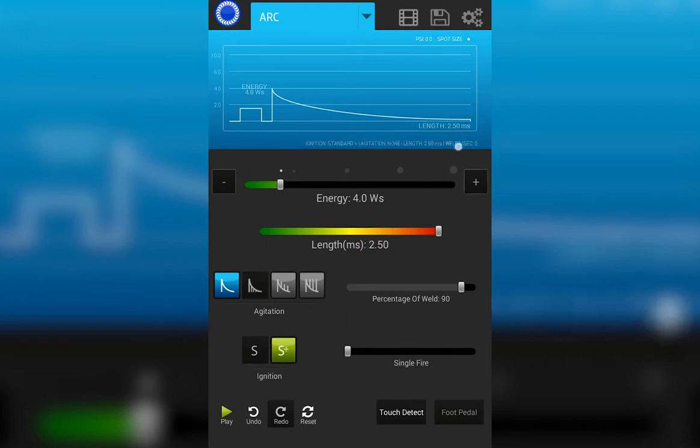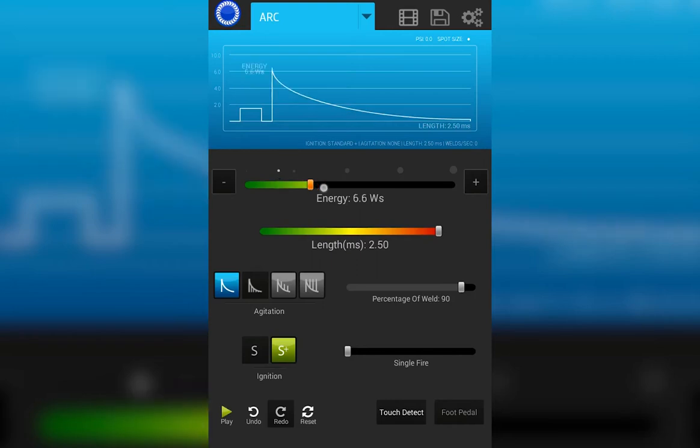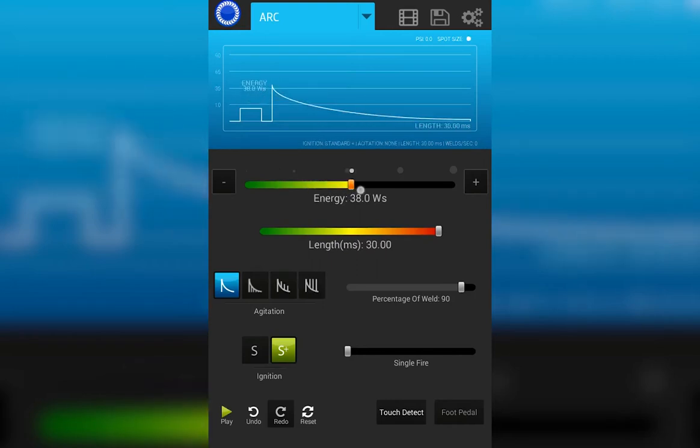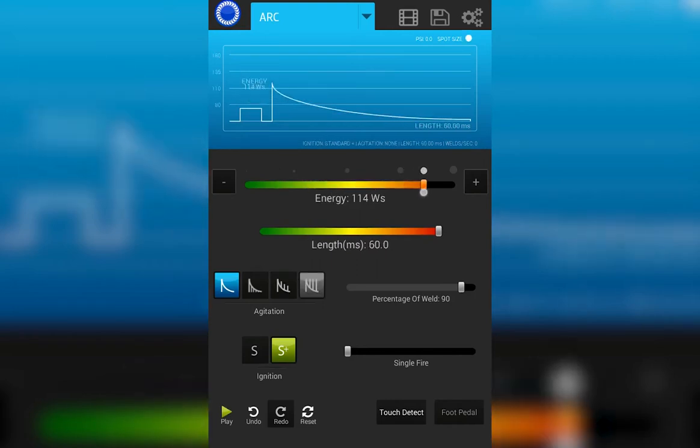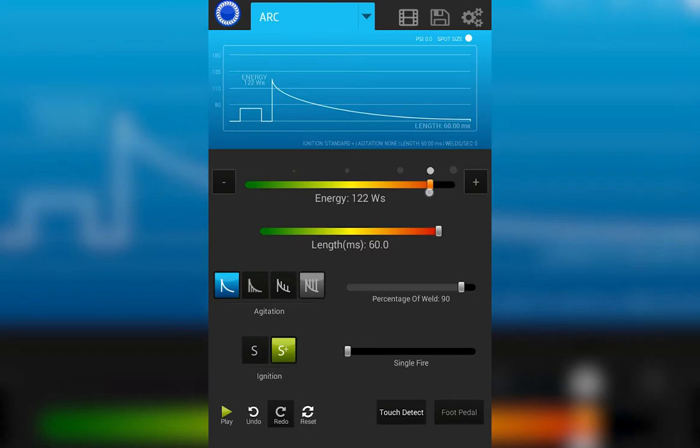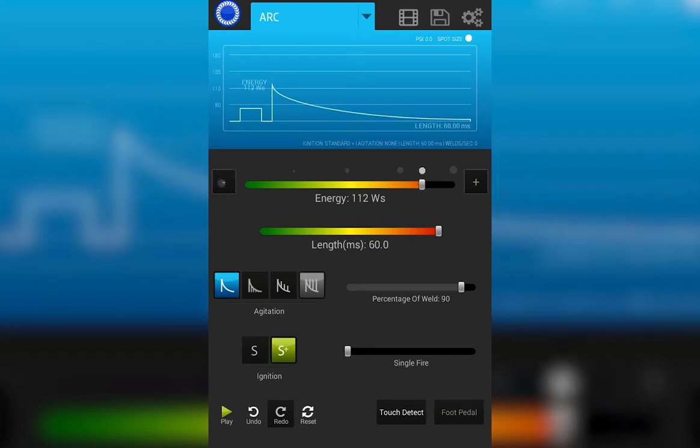Just underneath the weld graph portion of the screen you have the energy bar. This controls the weld energy. You can make adjustments by sliding your finger across the bar or by hitting plus and minus to the sides.